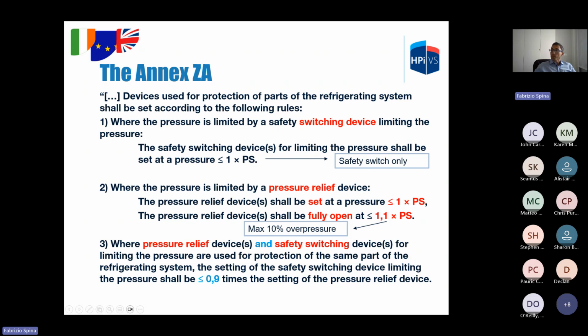Devices used for protection of the parts of the refrigeration system shall be set according to this rule. When only switching devices are used, honestly, I have never seen that configuration. The set pressure must be equal to the PS or lower. When a pressure relief device is installed, the set pressure must be equal to the PS or lower, and the pressure relief device shall be fully open at 1.1 times the pressure, the same 10% overpressure we saw before.